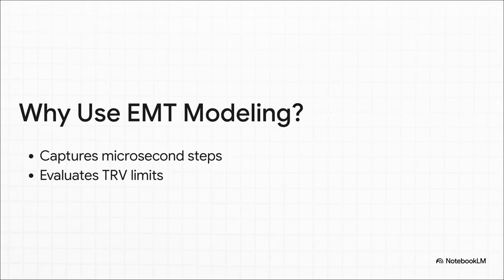EMT simulations utilize ultra-small microsecond-level time steps to catch these fleeting events. But more importantly, EMT allows us to model frequency-dependent effects and the nonlinear characteristics of equipment, like core magnetic saturation in transformers. It is also the only way to accurately evaluate transient recovery voltage, or TRV, which is that severe voltage stress that appears across the contacts of a circuit breaker the exact instant it tries to clear a fault.